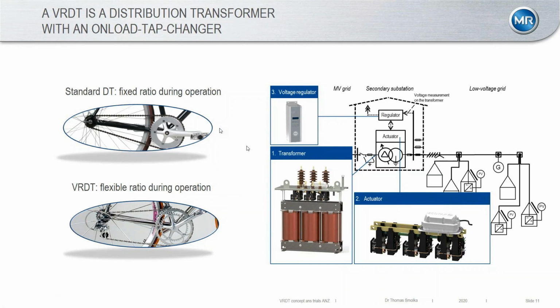...adjust the settings and add or subtract different windings to the transformer, and by doing so also change the ratio of a transformer and regulate the voltage for all connected customers. So that's a tap changer.